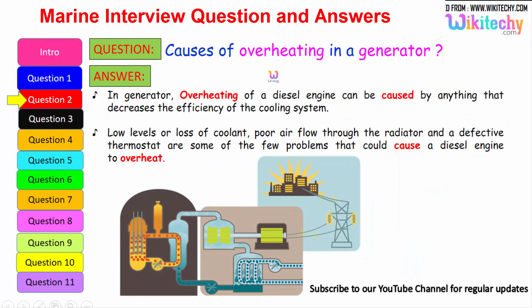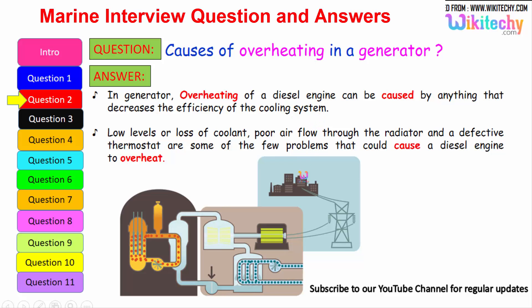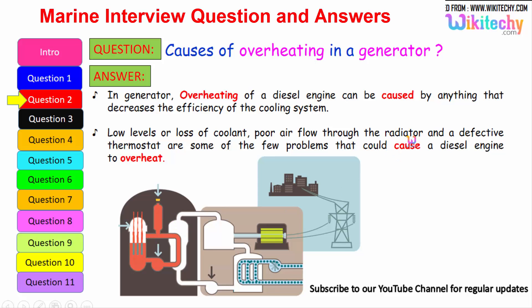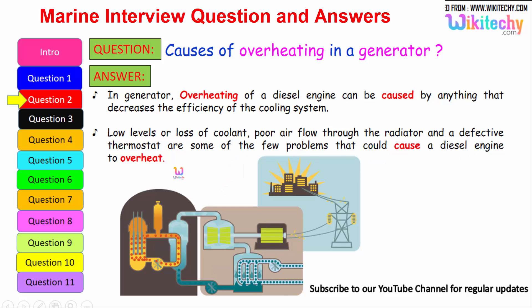Let's move on to the next question: causes of overheating in a generator. In a generator, overheating of a diesel engine can be caused by anything that decreases the efficiency of the cooling system. It can be due to loss of coolant or low levels of coolant, or poor air flow through the radiators, and a defective thermostat — these are some of the problems that could cause a diesel engine or generator to overheat.